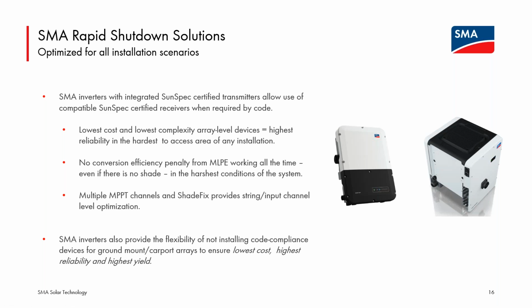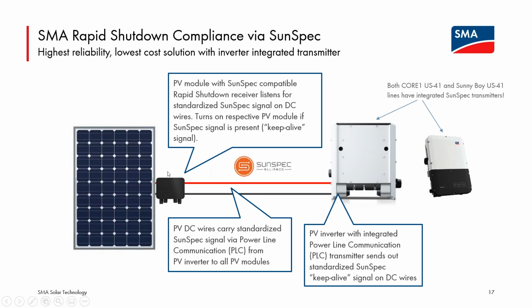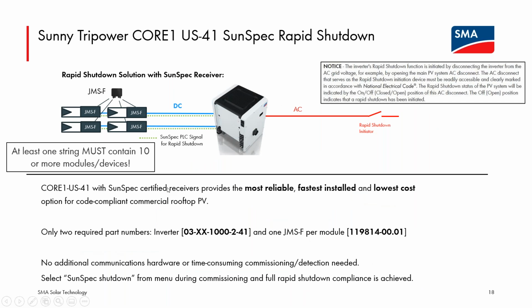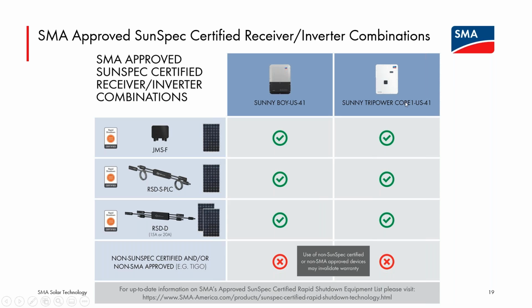My, again, very limited understanding of Canadian code is that there is not an inside of the array voltage requirement like there is in the more recent code editions in the US. So that provides a benefit that we're finally getting back in the United States based on a certain rapid shutdown listing for the CORE1. So if customers need that module level shutdown, we have simple code compliance devices that listen to a power line communication generated by a board pre-installed in the CORE1 from the factory. So there's no additional communications channel needed to comply with module level rapid shutdown, just the CORE1 US-41 and an SMA approved receiver device at the modules. So we have several options for pairing with the CORE1.